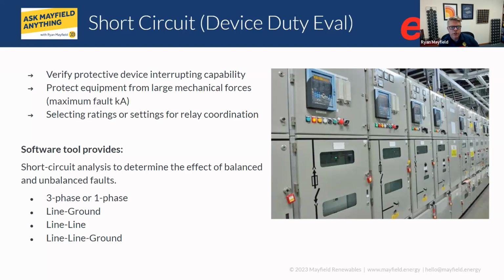So with that, Victor, is that something? So you mentioned the KA ratings, things like that. So does that require input from the utility? Do you need to know service size, conductor sizes, things like that, in order to properly get that information in to run these short circuit studies?